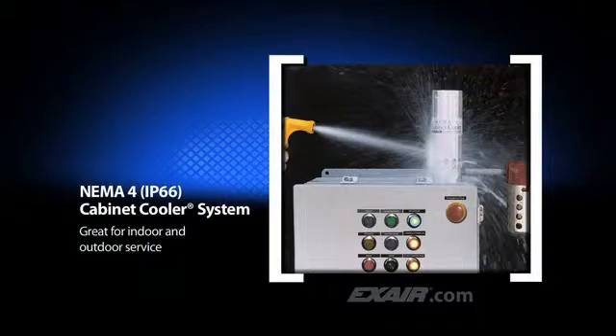They incorporate a low pressure relief valve on both the vortex tube and cabinet cooler air exhaust. This valve closes and seals when the cooler is not operating to maintain the integrity of the NEMA 4 enclosure.